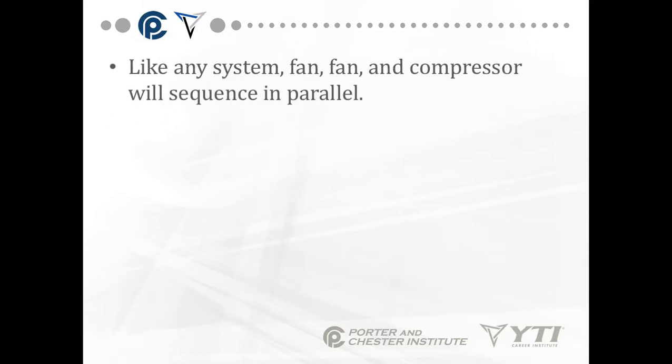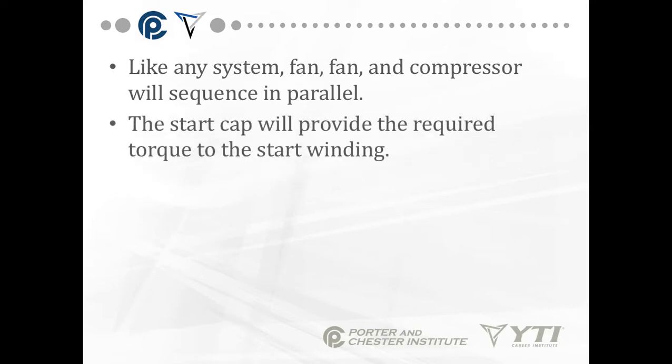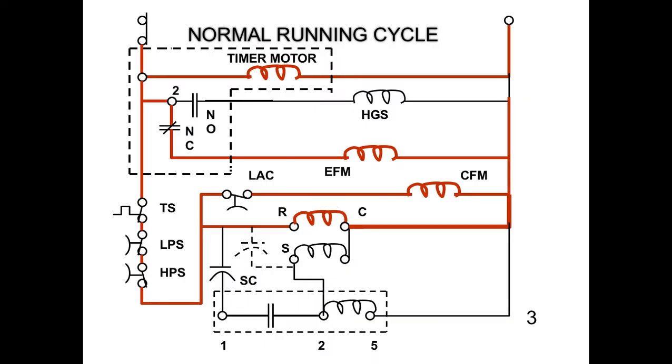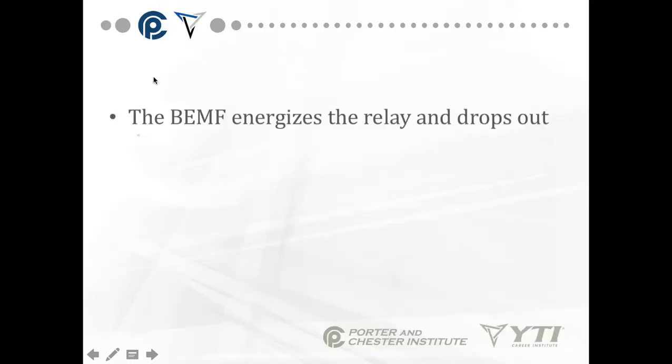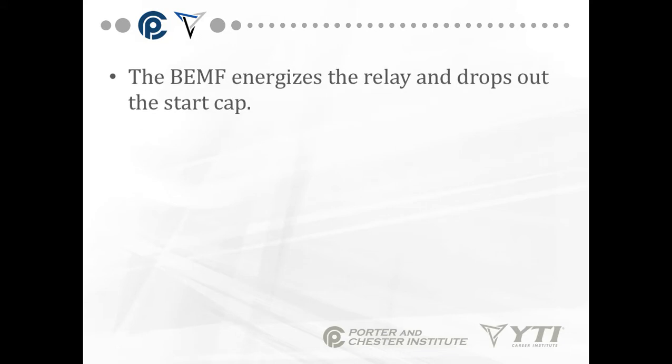So again, like any fan system, the fan compressor will sequence in parallel. The start cap will provide the required torque to the start winding. Now the motor's running. So the biggest difference here is that because the motor's running, 1 to 2 has opened, and that's caused by back EMF on pins 2 and 5, which has taken the start capacitor out of the circuit, and the start winding is no longer energized. So the system is running as the induction run part of the CSIR motor. Start winding is no longer energized. So the system is running in a cooling mode. The timer motor, the defrost clock, is starting to time how long the system is running.